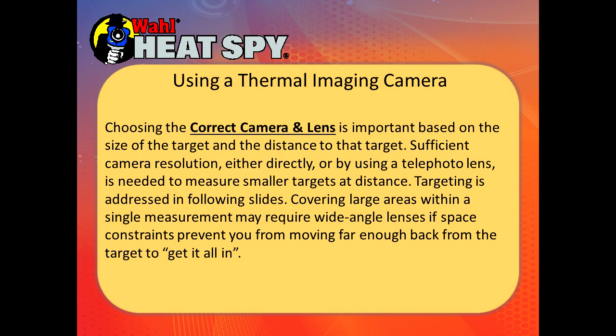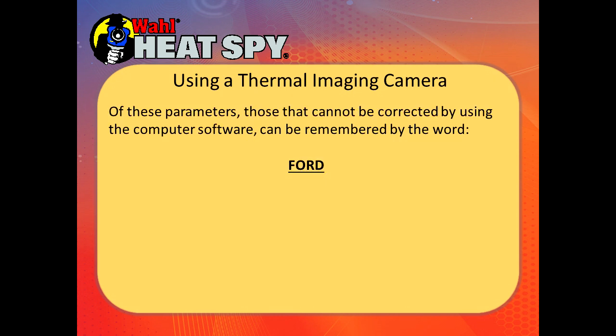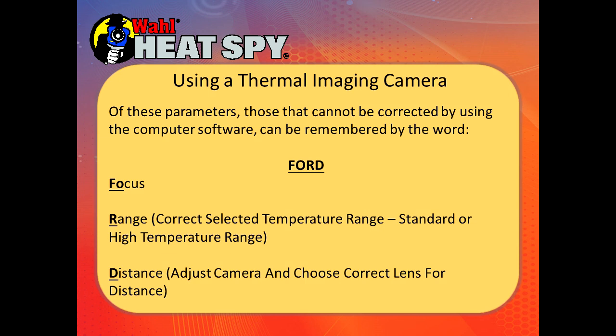Wide angle lenses are generally used for building energy measurements where you want to get an entire wall in one shot. Perspective means doing what is necessary to get a clear, direct line of sight to your target, moving around to get the best view. You also need to be aware of air movement over your target and how that will affect it. The parameters that can't be corrected by software are remembered using the word FORD: Focus, Range — you must have the correct temperature range selected — and Distance, where you need to understand the distance and have the correct lens chosen. All other things can be fixed in the software.